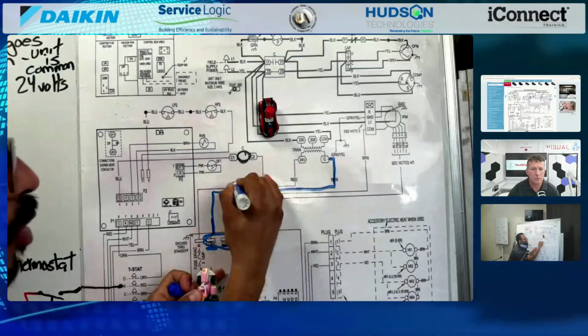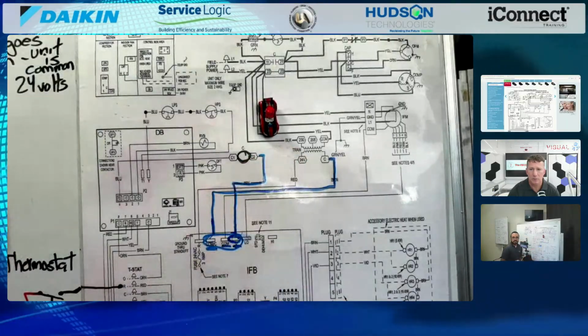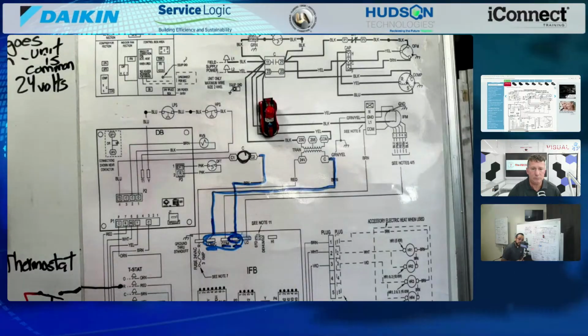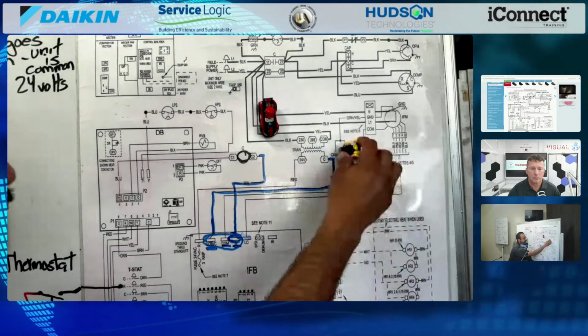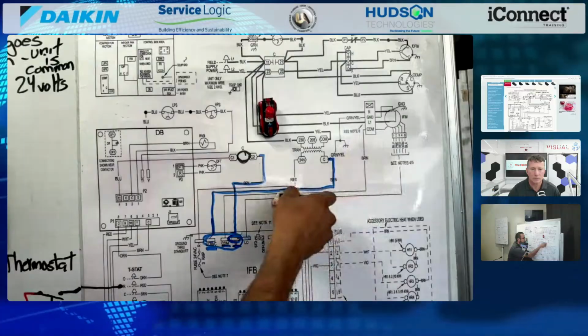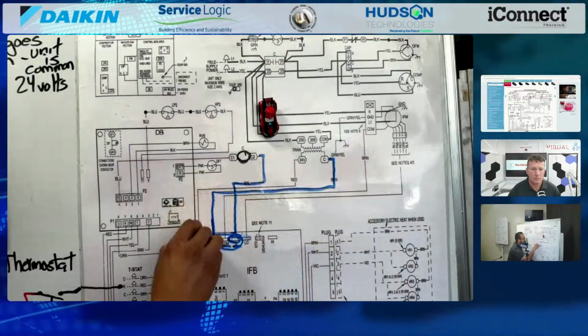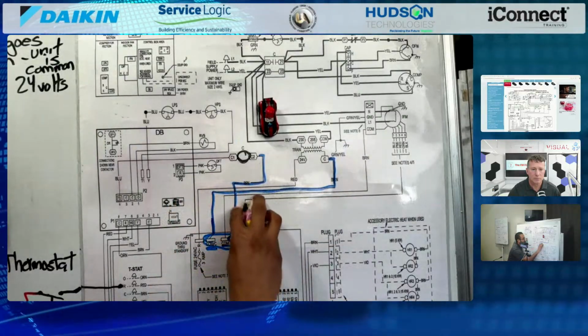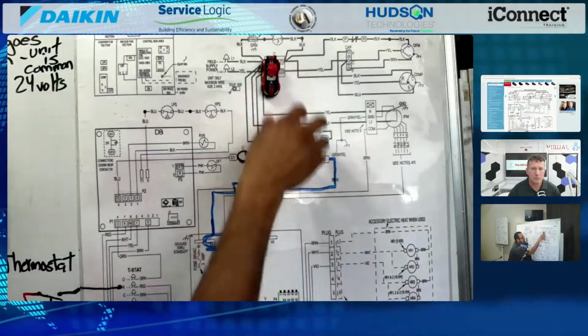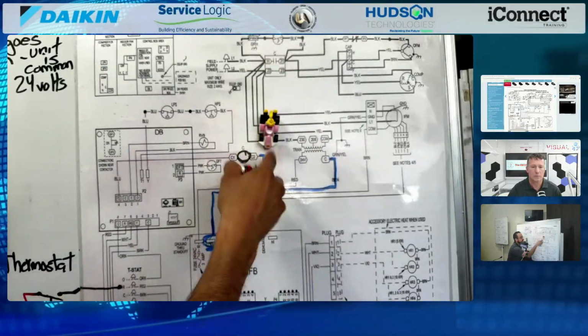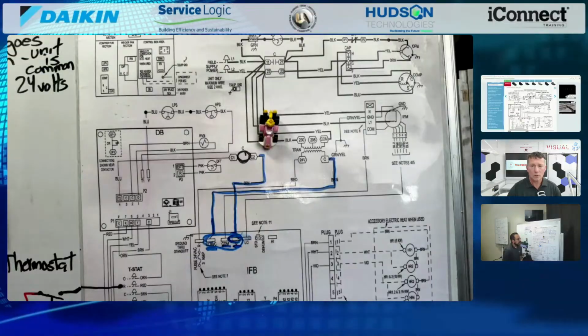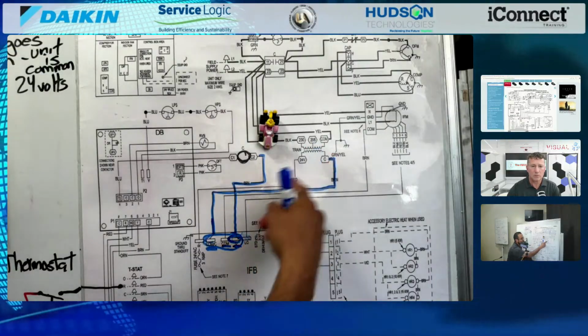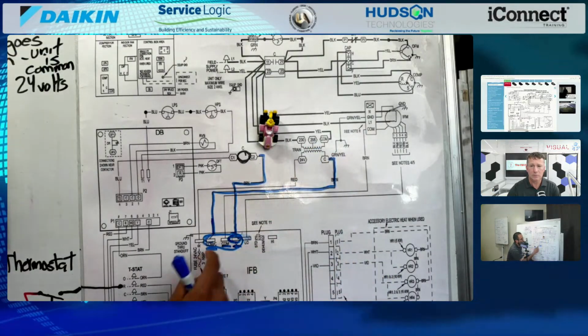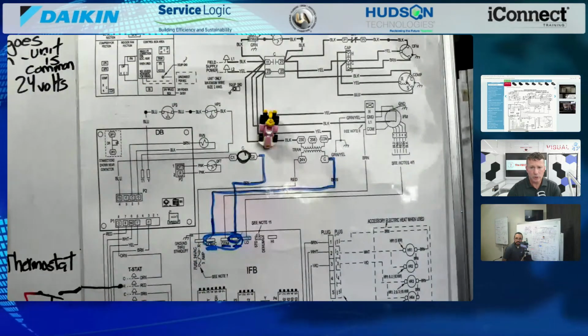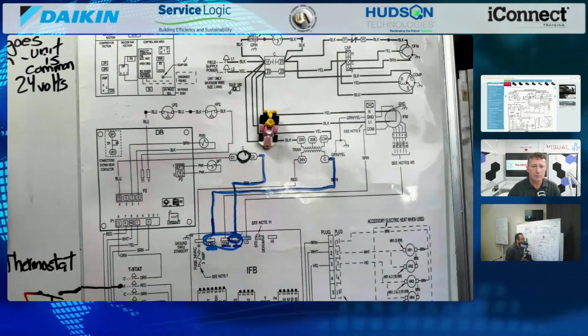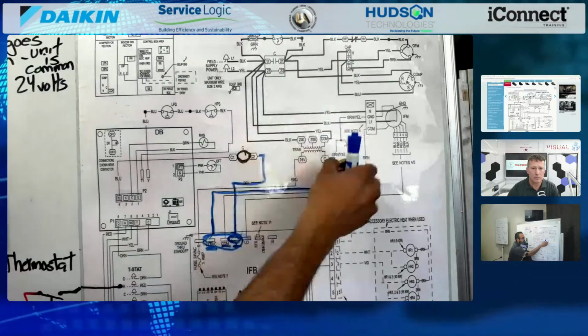If you follow it, that goes to my contactor coil. So you have a direct path, a home run. Peach is going along having a good time—there's no switches to go through. There's a path, and boom, she's already made it to the contactor coil on one side. Now, I'm not saying nothing can happen to the wire—the wire can break, the board itself could be messed up, the road could be blocked. Something can happen. But typically, common is home run.